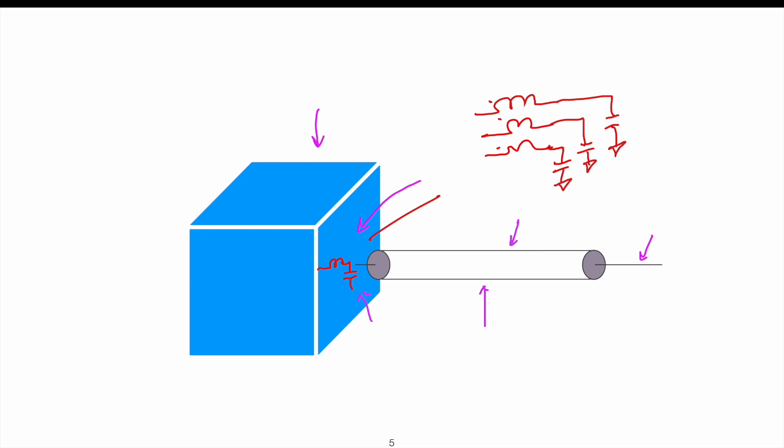And these capacitors are important. And as you can see, these capacitors, one end is connected to the signal or power wire you wanted to filter the noise. But the other end is very important. This end is often connected to the metallic enclosure itself, often what we call chassis connection. So these capacitors are connected to the chassis.